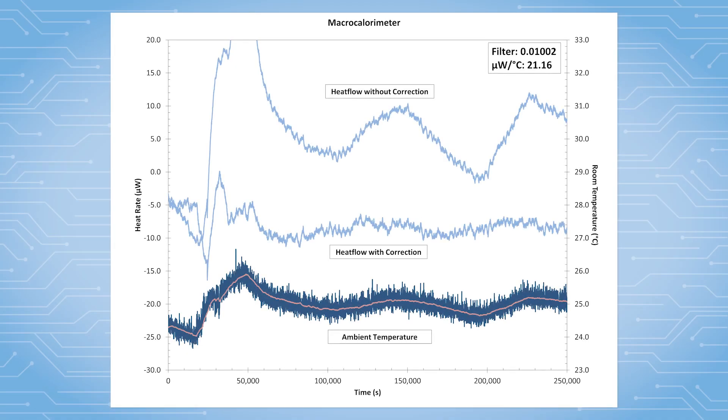In this example here, we can see what the data would have looked like if the heat flow correction was enabled compared to the signal that was collected without. If corrected, the signal would not display the same signature as the ambient temperature. Going forward, it would be beneficial to run with the heat flow correction enabled for this configuration to ensure optimal baseline performance.